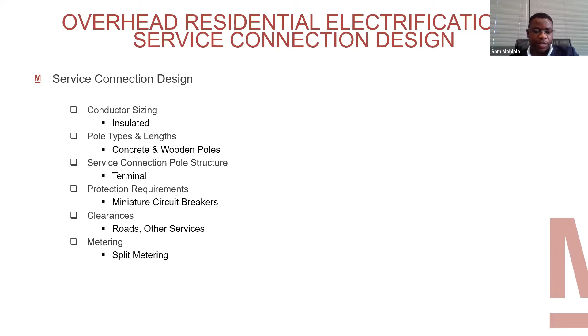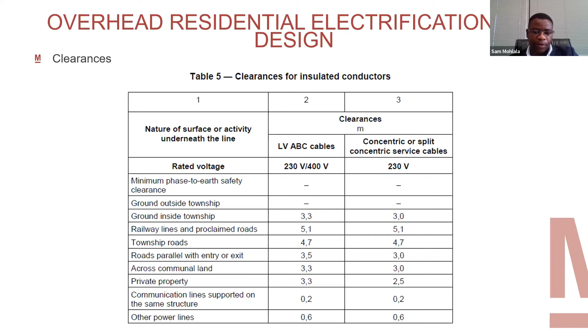Metering depends on the municipality as well. Some municipalities use split metering, others use smart meters or just direct metering, so that depends on the municipality or the supply authority. Then the clearances also have to be taken into account. This is a table that shows you the clearances of insulated conductors. From my left, in column 1 you have the nature of surface or activity underneath the line or rated voltage, in column 2 your LV ABC cables, and in column 3 your concentric or service cable. These are the tables that guide you in meeting the minimum clearance requirements.